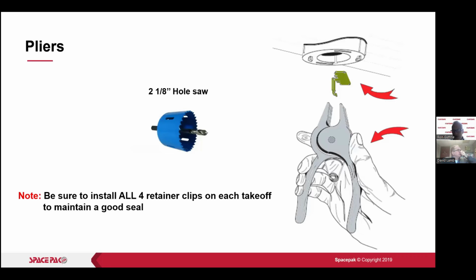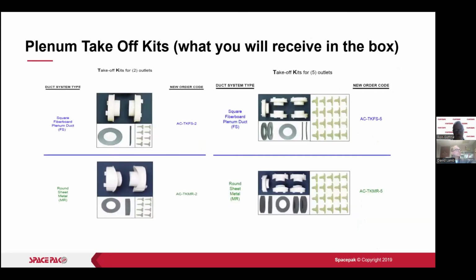Use all 4 of the clips. If you use 2, you could be rocking on there. But make sure that you use all 4 retainer clips provided on the takeoffs to make sure there's a solid seal on that gasket. Here's how the plenum takeoff kits come.